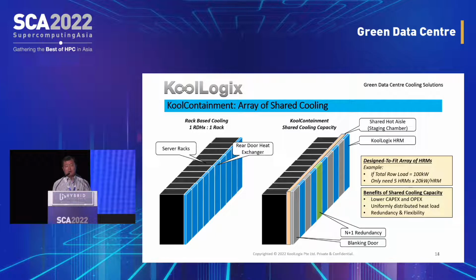On the left-hand side, we have shown a typical rear door heat exchanger. As you know, we need one rear door heat exchanger per rack, so it's a one-to-one match. On the other hand, our KoolLogix system also incorporates a KoolContainment, to which the racks are attached from one side, and on the other side we have a heat removal module attached. Each HRM is capable of removing about 20 kilowatts. So let's assume these 10 racks altogether dissipate about 100 kilowatts. Then we need only 5 HRMs, not 10. The picture on the right highlights that the blue ones are HRMs and the gray ones are blanking doors, just a sheet metal cover, because we don't need an HRM there. In addition, we can add one additional HRM, if and as desired, to be used as a redundant HRM.